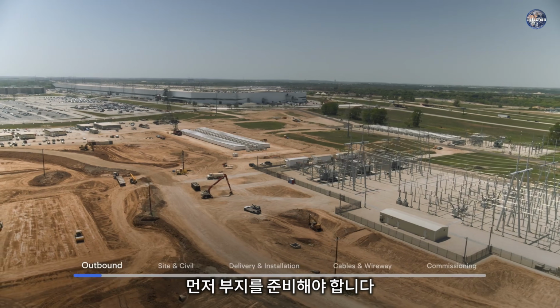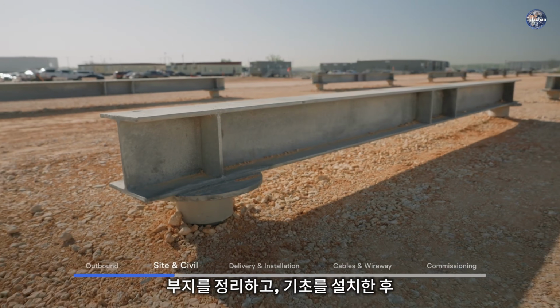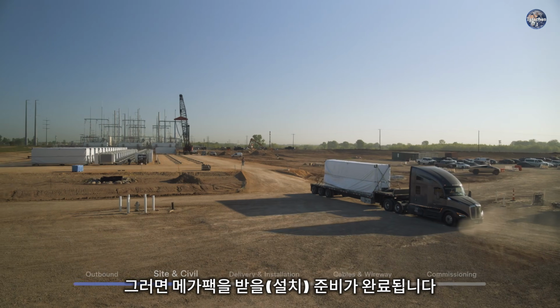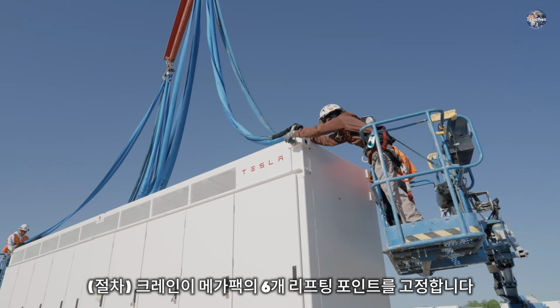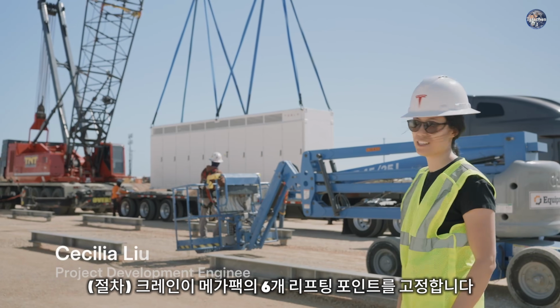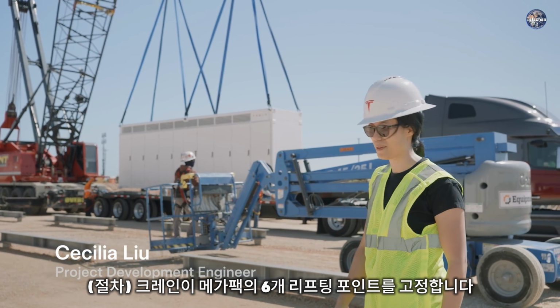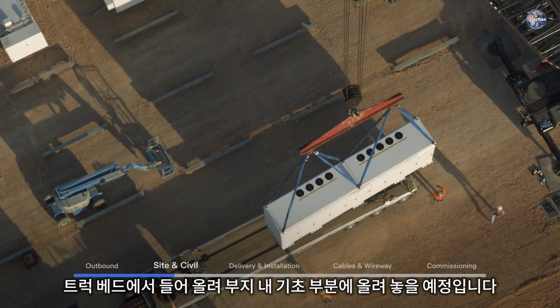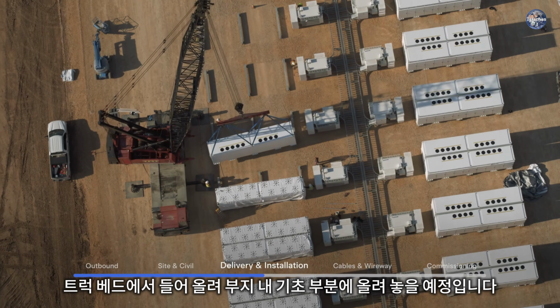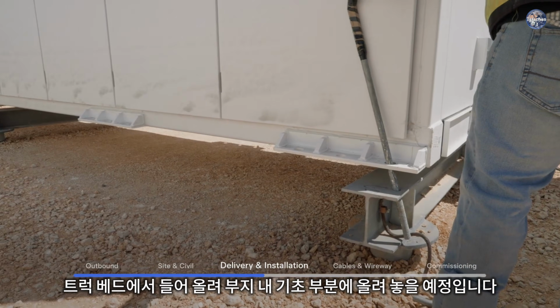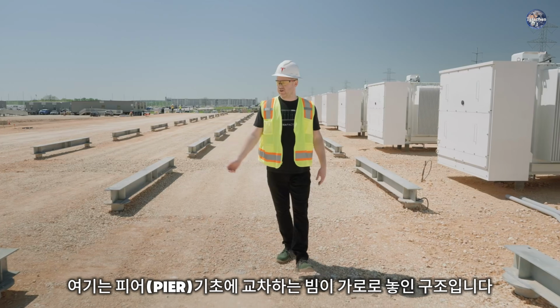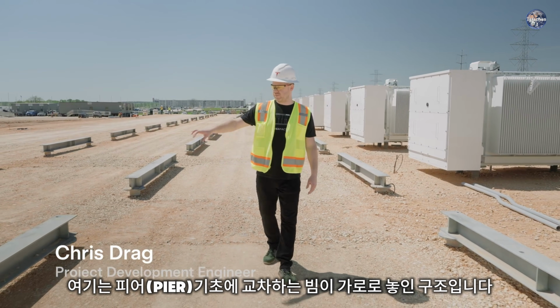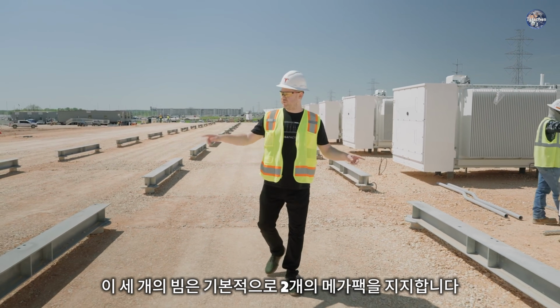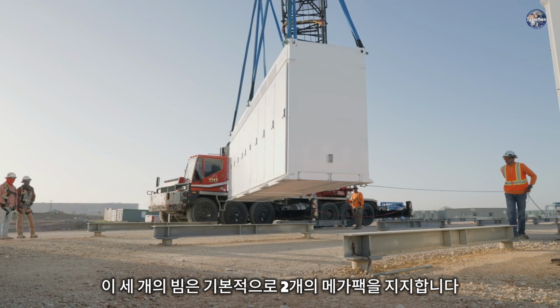First, the site needs to be prepared, the site needs to be cleared, foundations need to be installed, and then the site is ready to receive Megapacks. So they've got the crane anchored into the 6 lifting points on the Megapack right now. They're lifting it off the bed of the truck, and they're going to swing it over and place it on these foundations here. What we have here is pier foundations with a beam that runs across. Basically, these 3 beams will support 2 Megapacks back to back.